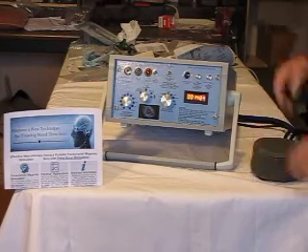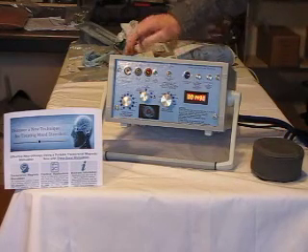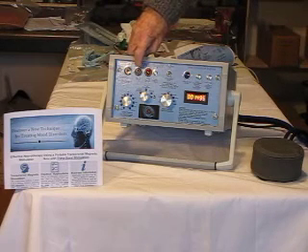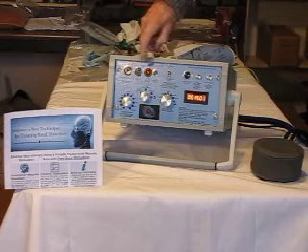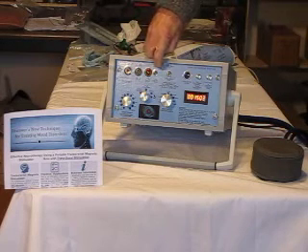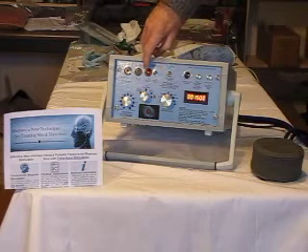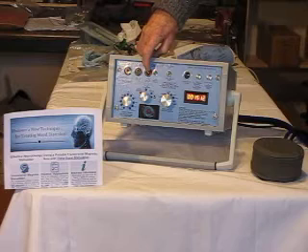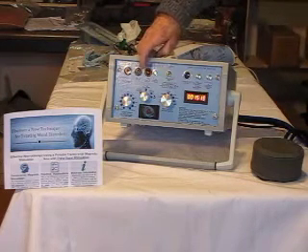This new TMS unit has power on and off. It has a circuit breaker that can be reset with the push of a button, and an indicator showing the state of the power supply. A neon light shows the high voltage — it's about 360 volts — through a bank of capacitors.